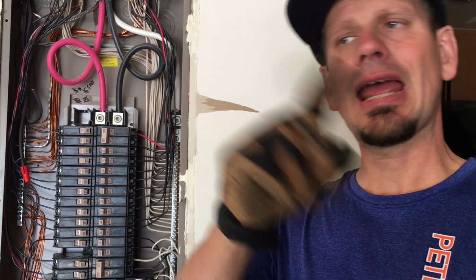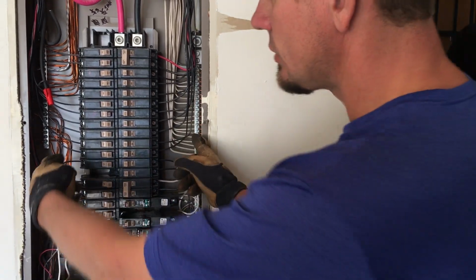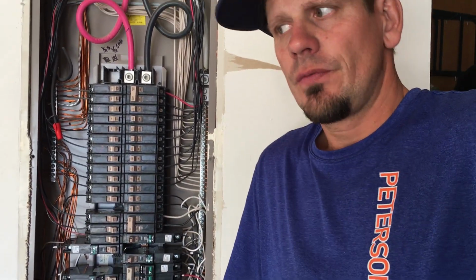Well, I'll just unscrew the light bulb. That helps you on the grounded conductor, the white, and if you're going to the ungrounded conductor, the hot or the black or the red, yes, that helps. But it doesn't help when you're going neutral to ground. Why? Because your ground is coming through. It still can feed through a breaker if the breaker neutral is there and it's on. And it can still backfeed through the ground, and you're still backfeeding through these 2 bars. So if you're picking up 60 ohms, that just means you're reading through a bunch of light bulbs, and it looks like it's tripping because of that.